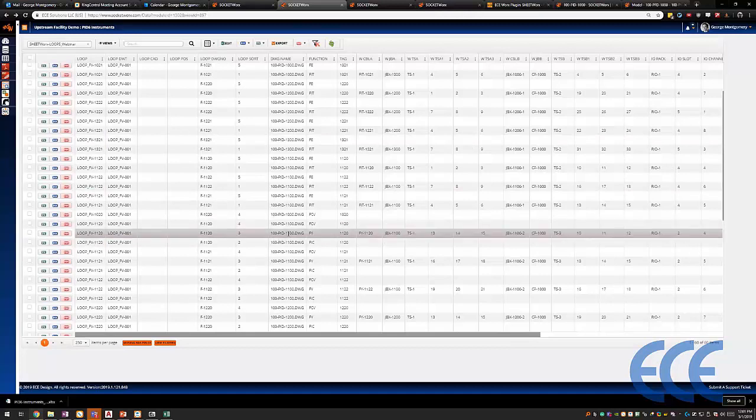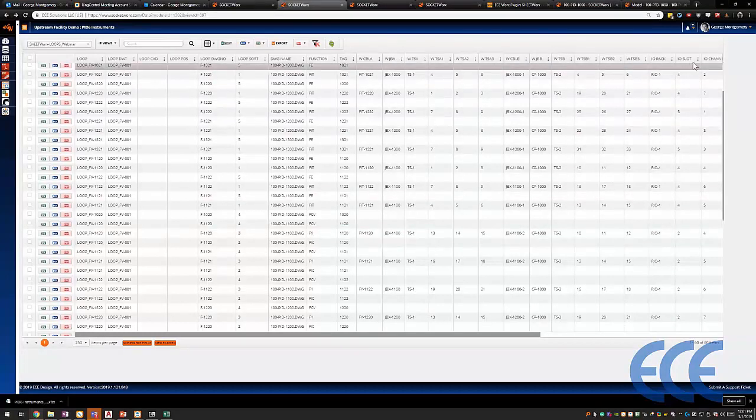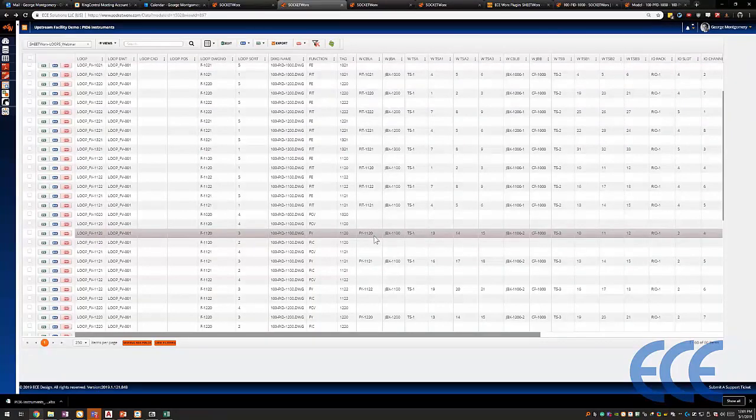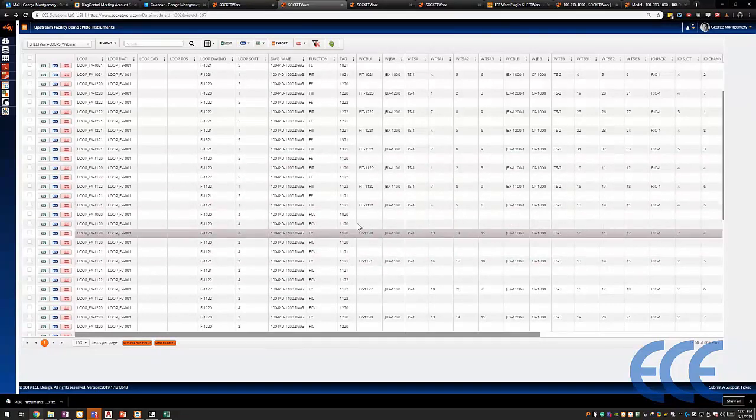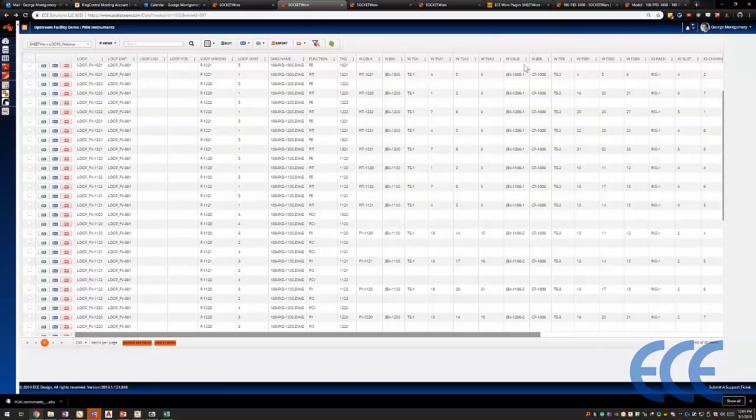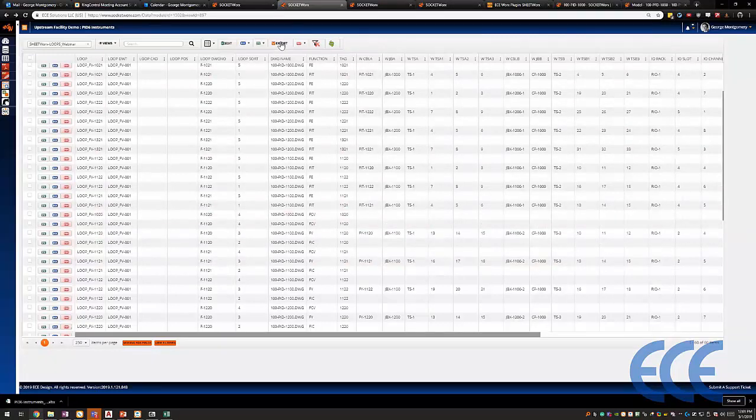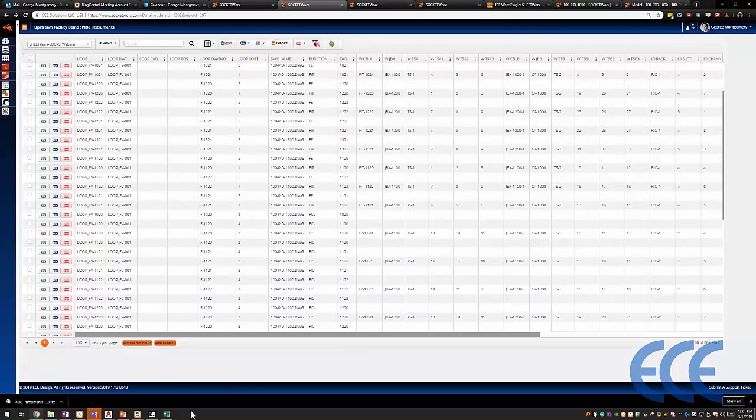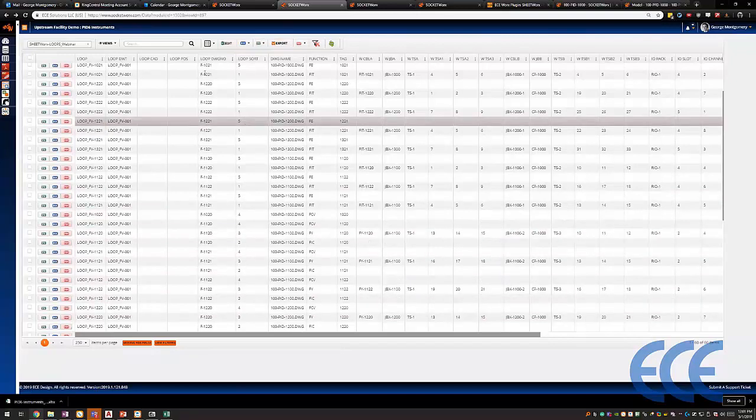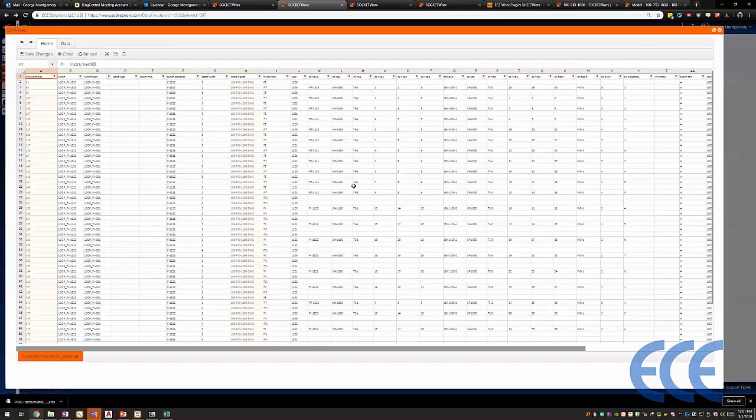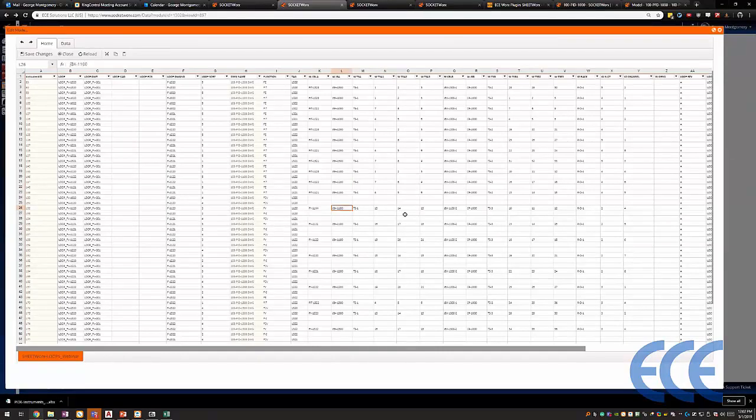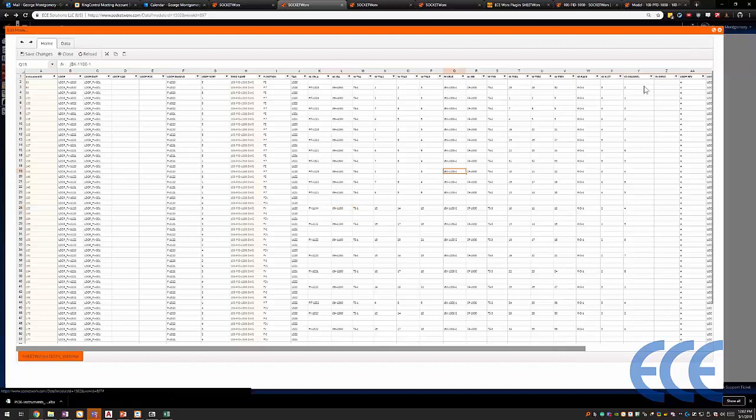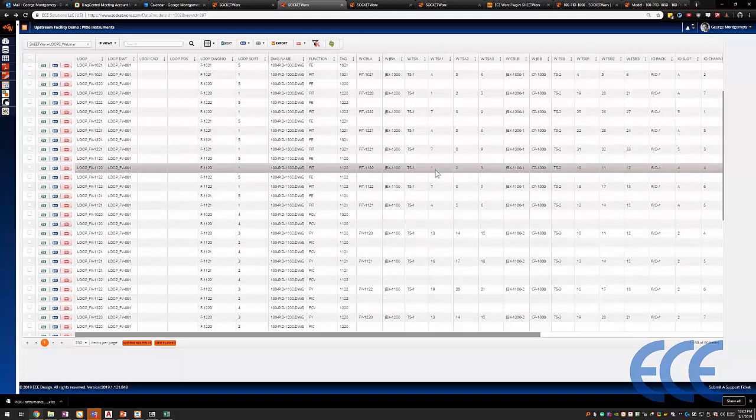So this loop, this 1120, that came from P&ID 1100.dwg. Everything else here that I've got as a column at the top, this is data that I've inputted manually. We've got a designer in Chicago, Nate Patton, who did a ton of work to get this set up for me. All of the column data that you're looking at here is set up in SOCKETWorx itself so that I can quickly just say Export and then create a new worksheet that I can create all my drawings based off of. You could edit this inside the interface if you wanted. It's not just a view-only type thing. If I wanted to make some edits to FY1120, I could make those edits and then Save and Close, Export. I don't want to make that edit, though. I'm going to go ahead and close this, discard it.